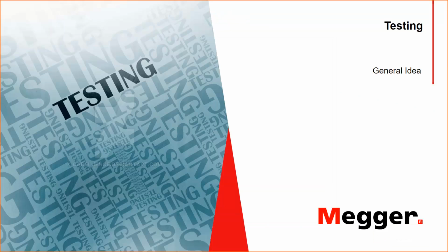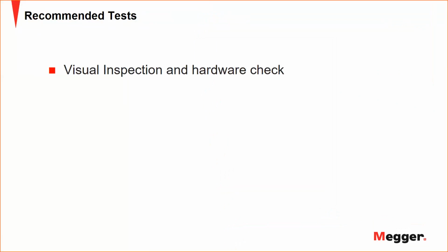So when I talk about testing, what do I mean by testing a relay protection in a general idea? The recommended tests that I would usually do, before you start any injection or checking any values or any setting, I would suggest doing a quick visual inspection and maybe a hardware check. In this visual inspection, you will inspect the relay having no burning marks, no electrical issues, no alarms saying it is faulty, it is working in a healthy state.